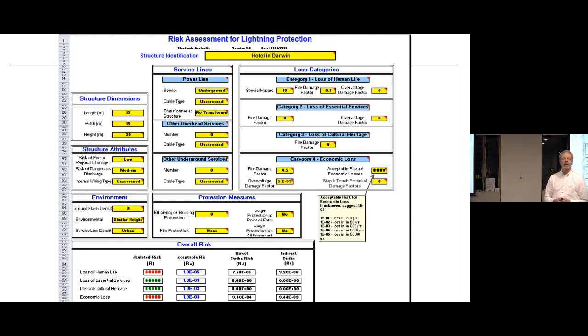Then we look at the protection levels, protection measures. The efficiency of building protection is actually whether you've got lightning protection already on the building. So that's going to be 0 unless you have some form of lightning protection. Then on the right, some of the letters have disappeared, but that's surge protection at point of entry, whether you've got that there, and then underneath that is surge protection at your distribution boards. And to the left of that is whether there's fire protection and whether that's manual, automated, or not at all.